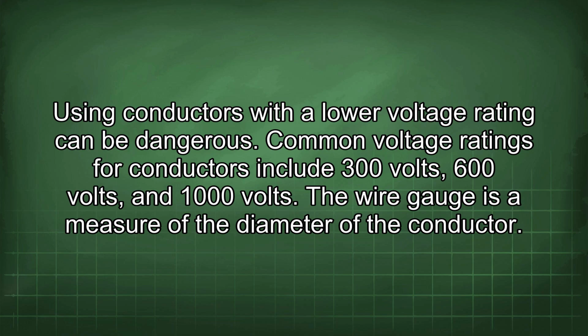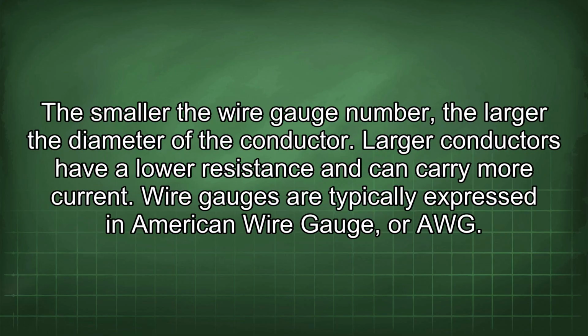The wire gauge is a measure of the diameter of the conductor. The smaller the wire gauge number, the larger the diameter of the conductor. Larger conductors have a lower resistance and can carry more current. Wire gauges are typically expressed in American wire gauge, or AWG.